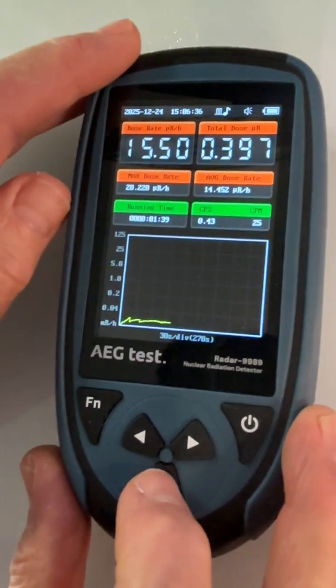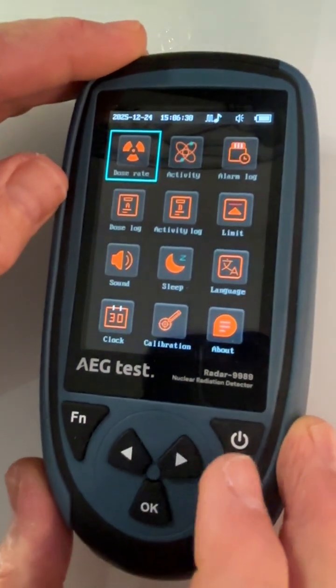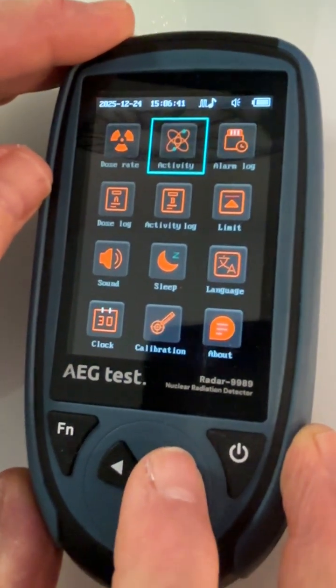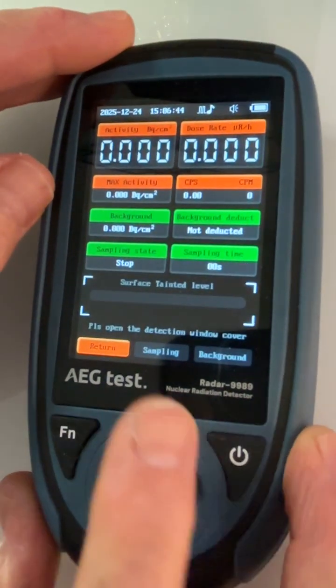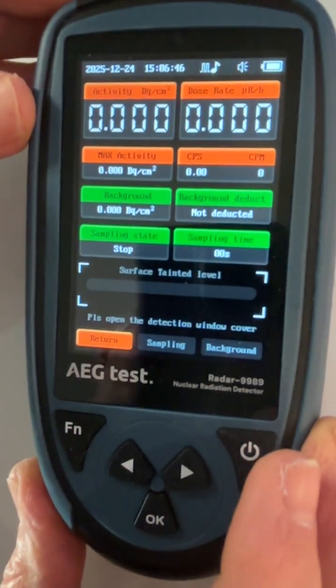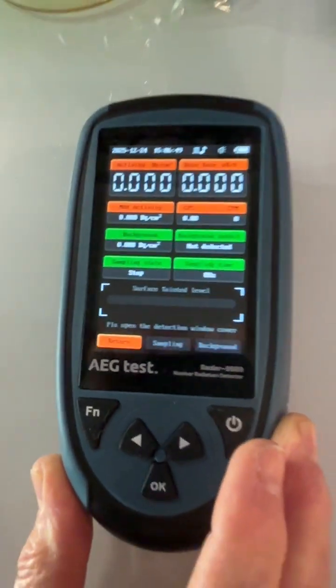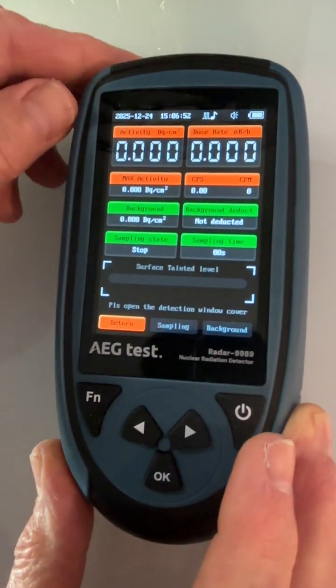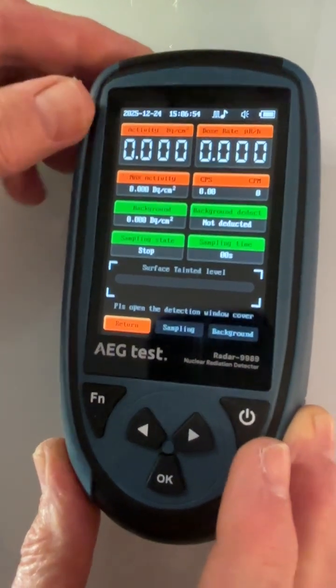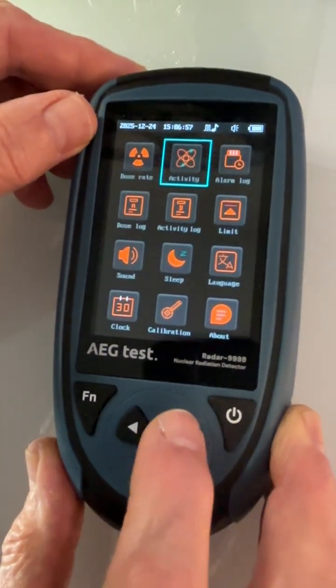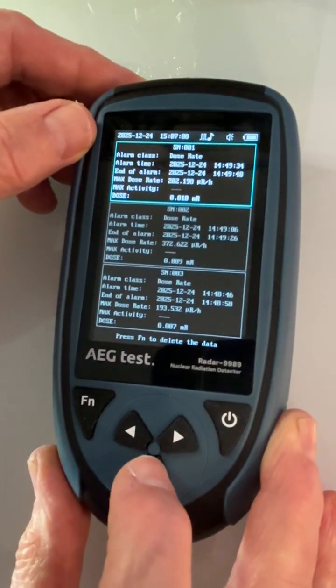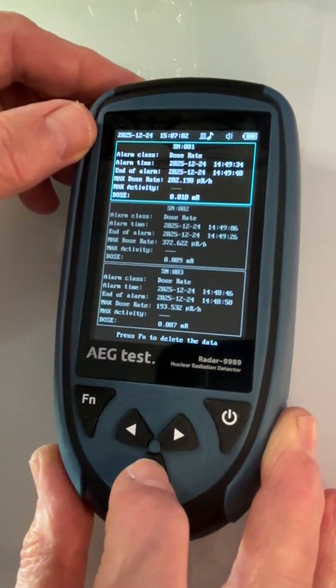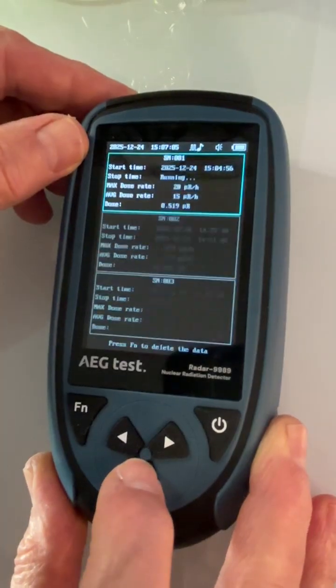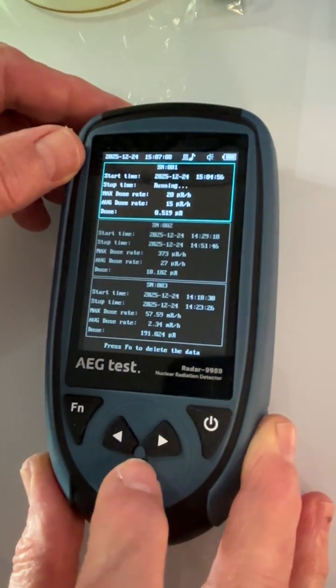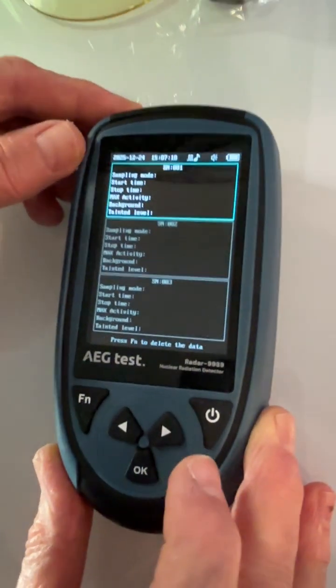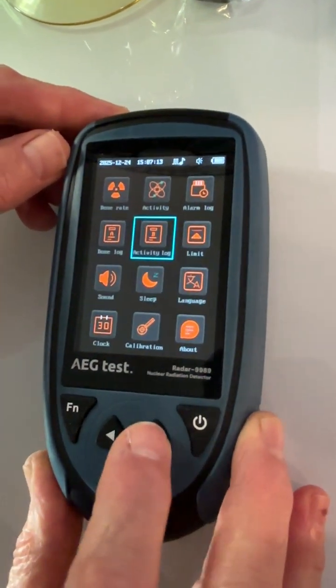We'll go through the menu settings here real quick. You're already in the dose rate mode. That's where you were. This is the activity mode. I don't find much use for this. If I do need to do an activity or contamination measurement, I will just go to a clean area and then just do a scan with the device. Okay, so that's that. This is the alarm log, which does alarm that information, and it will log it. This is the dose log. And of course, we use the activity function. This is the activity log.